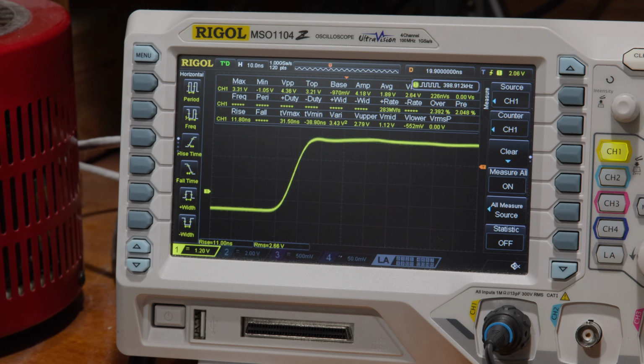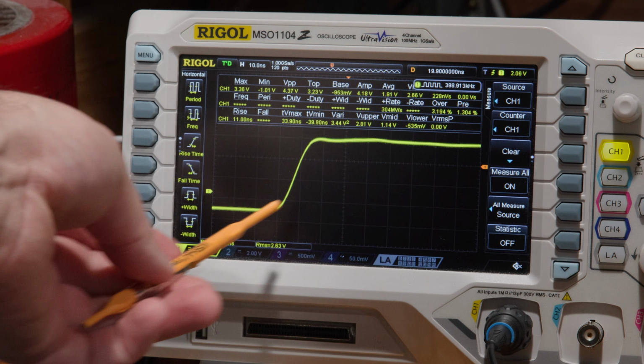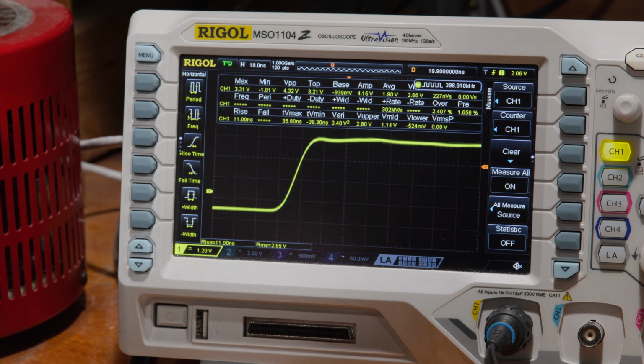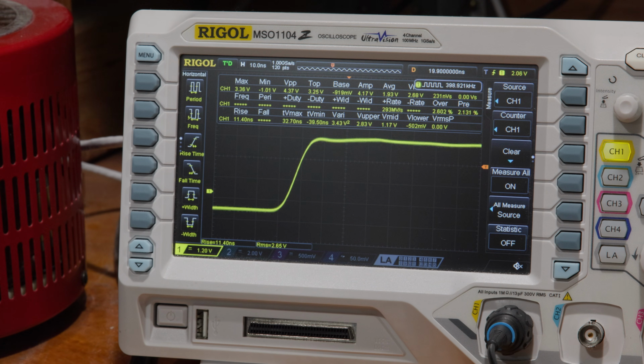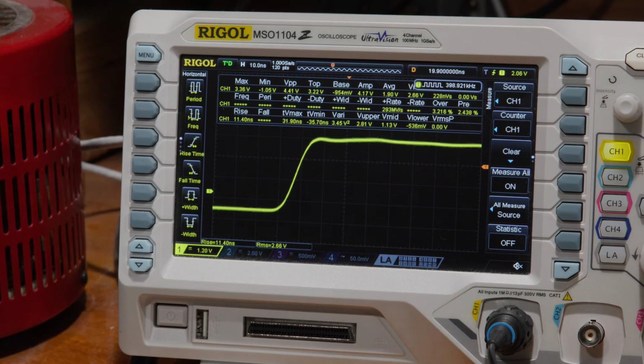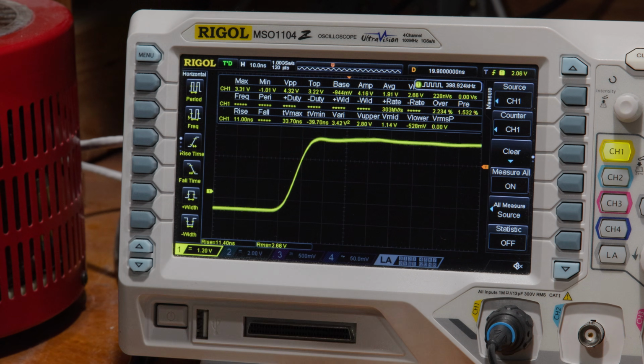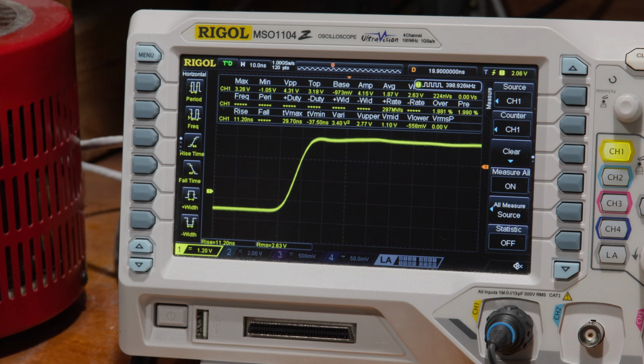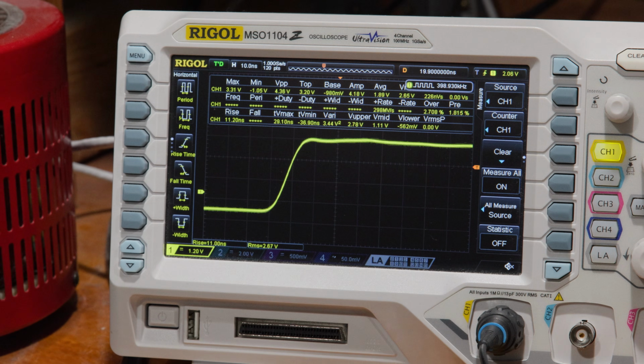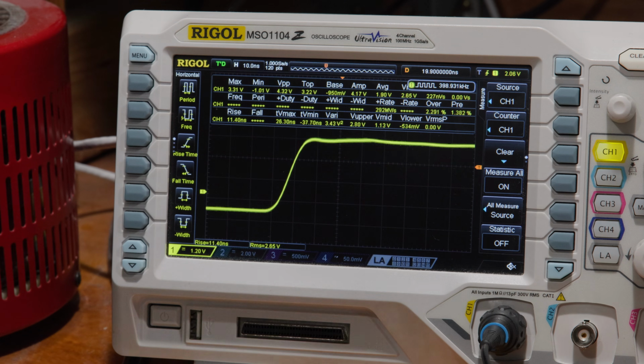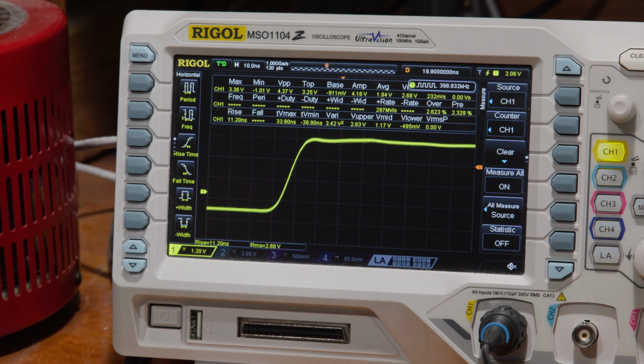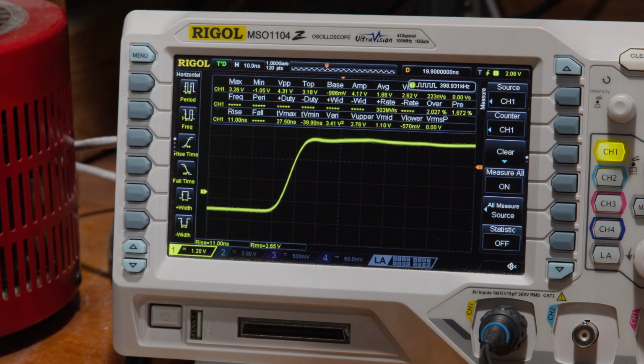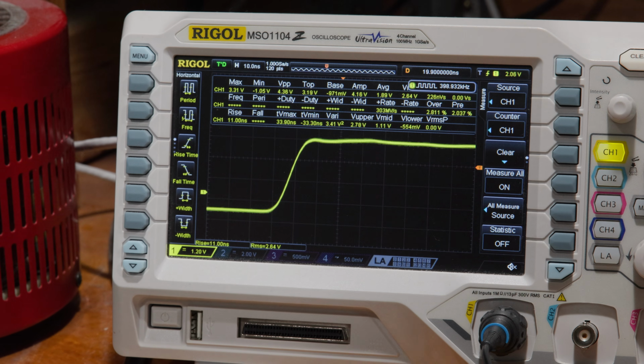Okay, we have a square edge that's looking better. However, our rise time is a bit light. It's supposed to be 10 to 15 nanoseconds, and we're down at 11 nanoseconds, so it's slowed up a little bit, but within 15, that's not bad. 11's good. That's right in the middle of the rise time, and we have a nicer square corner for the Z-axis compensation. Now, this is brightness. Any aberrations in this waveform would be fluctuations of intensity on the display and a couple of other things. So that is what we are adjusting at this point.